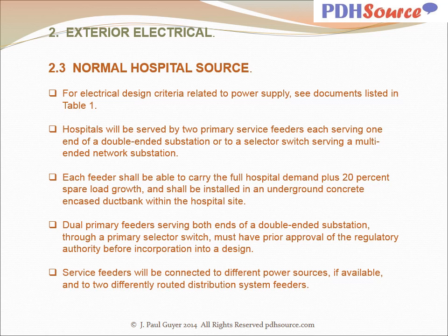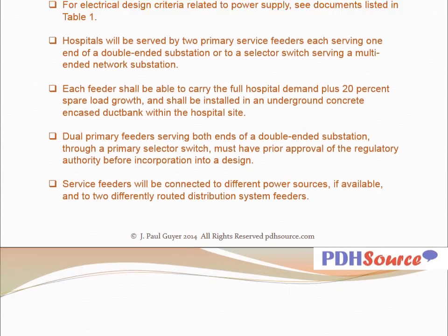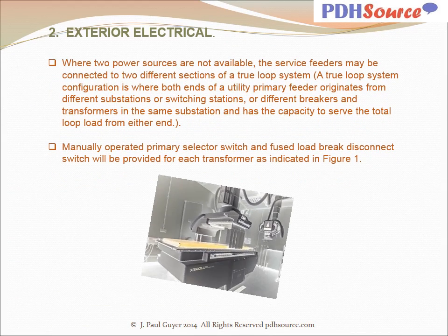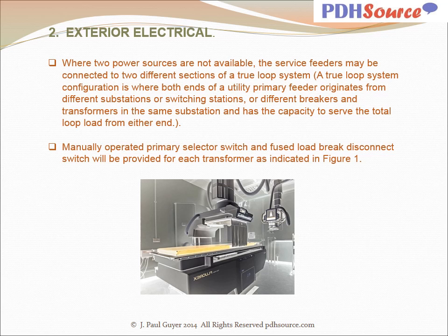Dual primary feeders serving both ends of a double-ended substation through a primary selector switch must have prior approval of the regulatory authority before incorporation into a design. Service feeders will be connected to different power sources if available, and to two differently routed distribution system feeders.